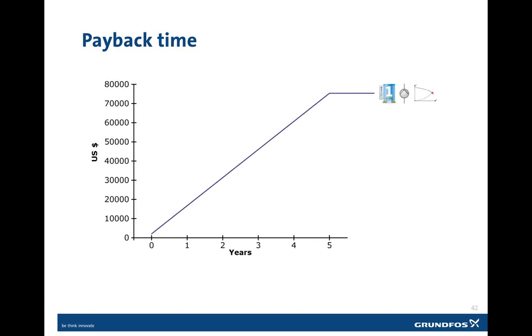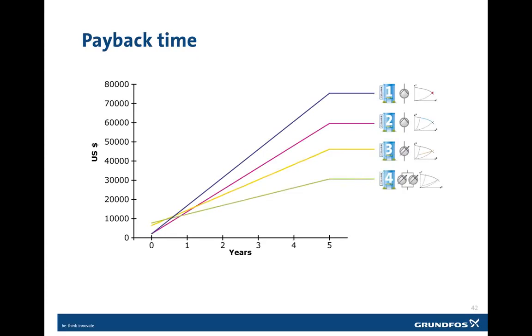So the first is our single pump operating at a single constant speed at a constant flow. And then the second is our single pump operating at a constant speed in a variable flow mode. Then the third selection is the single pump operating variable speed in a variable flow. And the fourth is our 2 sequenced parallel pumps operating variable speed and variable flow. So where these curves intersect determines what our payback period is for each of the pumps.